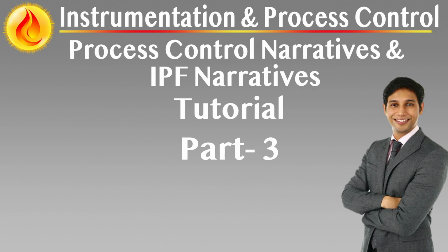Integration with other documentation. Cause and effect diagrams are cross-referenced in the IPF narratives but are maintained as standalone documents. They are essential inputs to functional logic diagrams, FLDs, system configuration in the safety PLC or DCS, verification and validation procedures during FAT and SAT, maintenance override grouping, alarm management systems, and safety lifecycle tools.